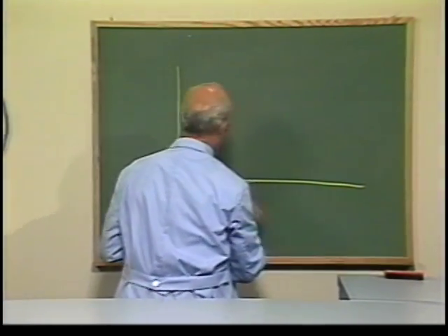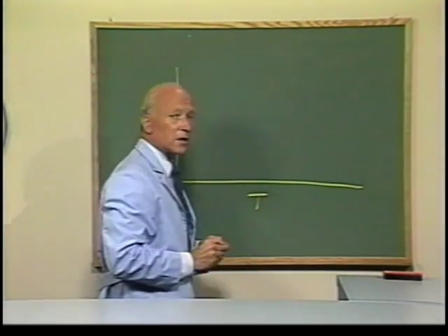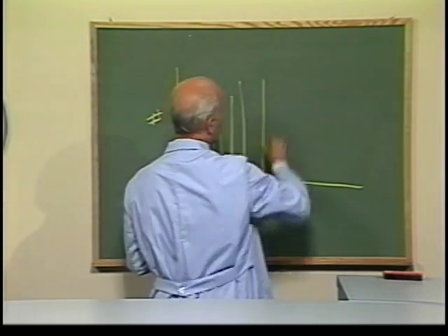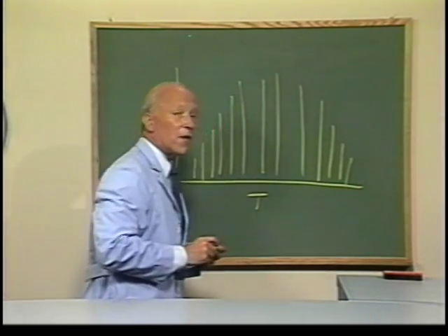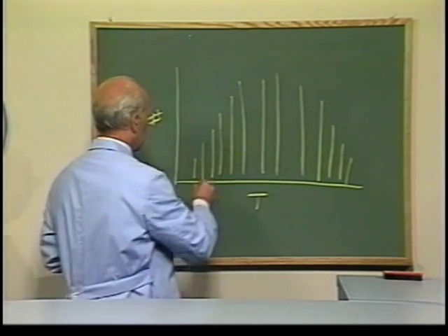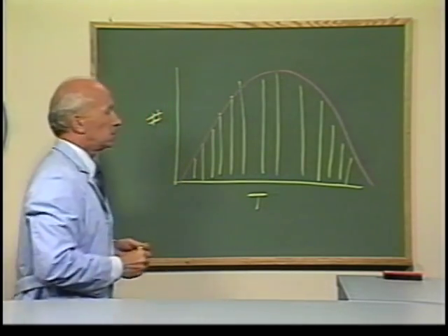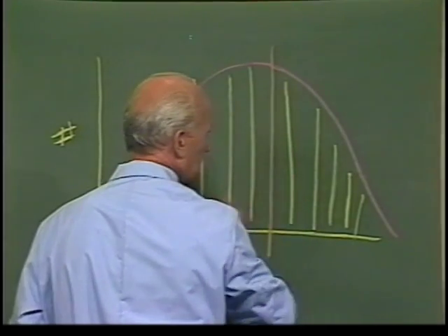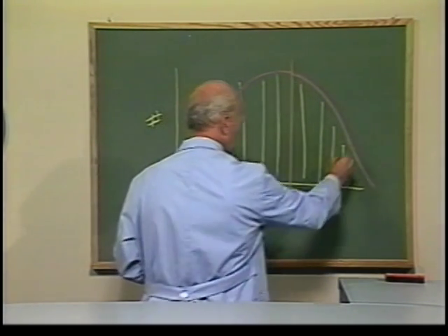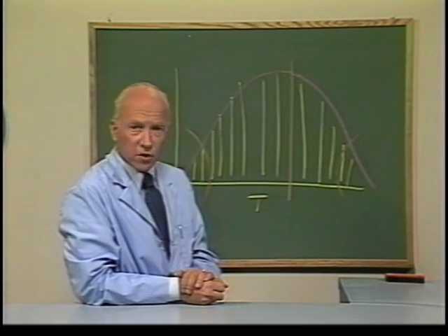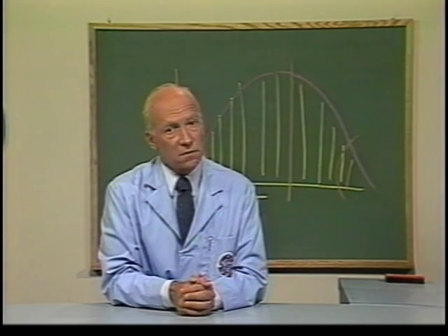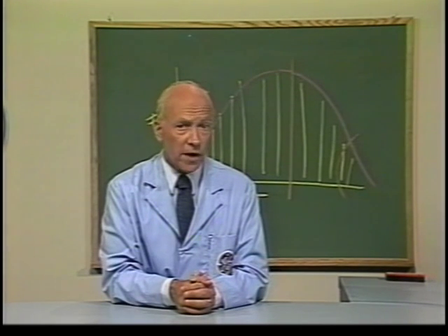For example, take one-third horsepower, six-pole, 230-volt direct drive motors. We may have several hundred different OEM models of that rating. If we plot the torque of all those models on a scale of low to high, we find a few with very low torque and a few with very high torque, with the majority falling in between — forming a bell-shaped curve. A replacement motor designed with a torque value slightly higher than the peak of the bell curve will successfully serve as a replacement for the majority of these OEM motors. Motors that fall on the ends of the curve may require an exact replacement or be served by another bell curve. Similar curves are plotted for watts, efficiency, etc., and taken into consideration for the final versatile replacement motor design.